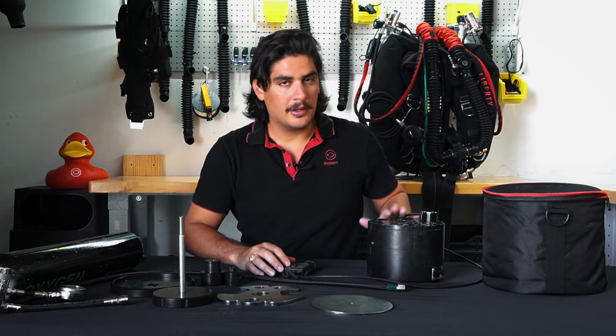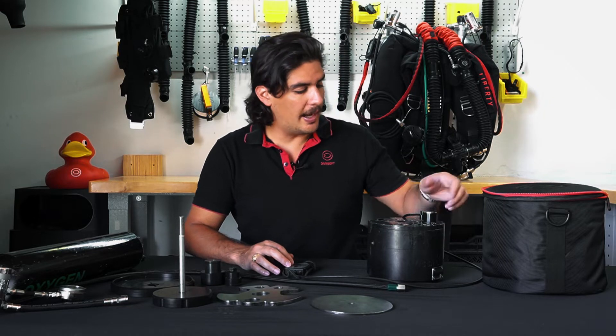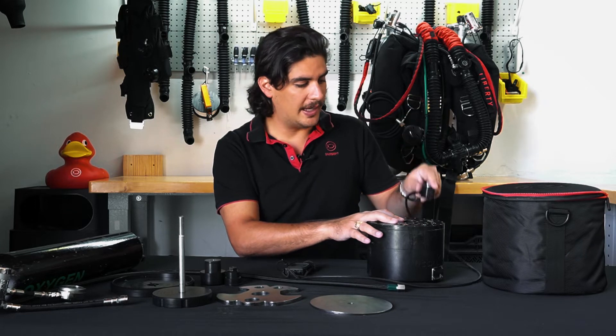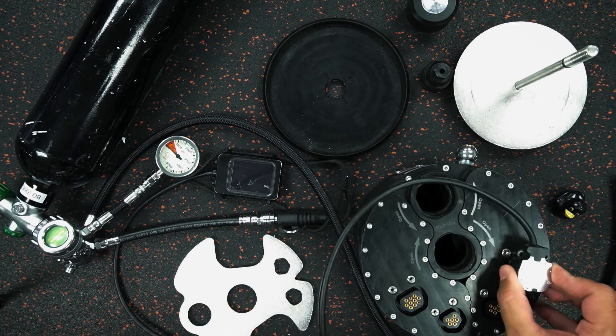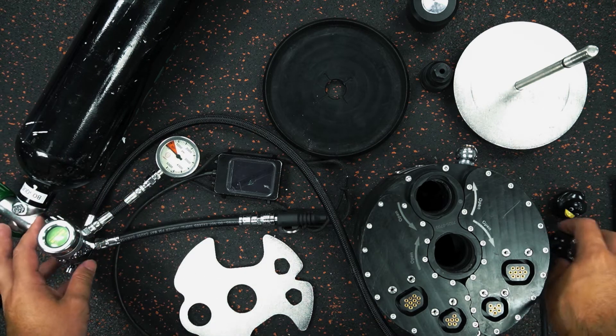I have my Liberty head, I have it turned on, but I removed the handsets, the heads-up display, and the buddy display of the head. I also removed the screws of the handset itself, so I have it just plugged in. And then I have an oxygen cylinder, I have my oxygen regulator, and I have a low-pressure hose. This hose is going to feed directly into the head.